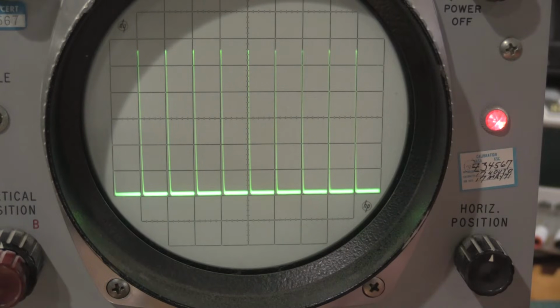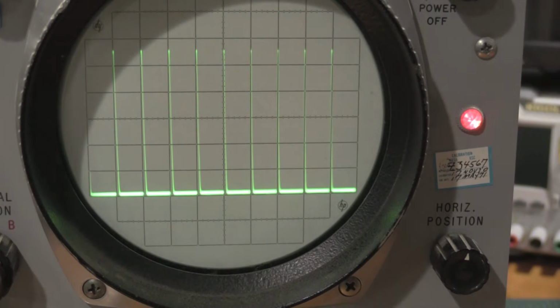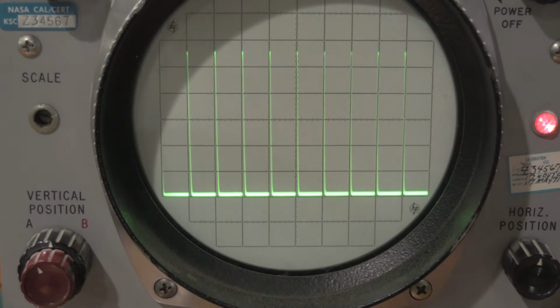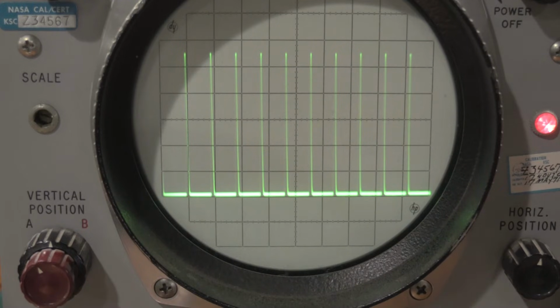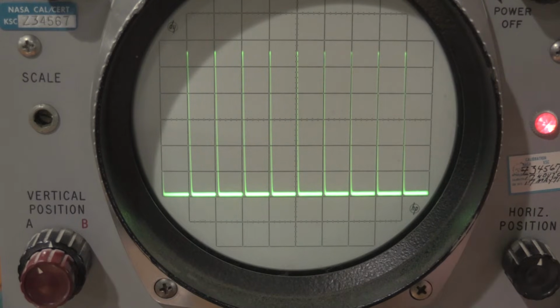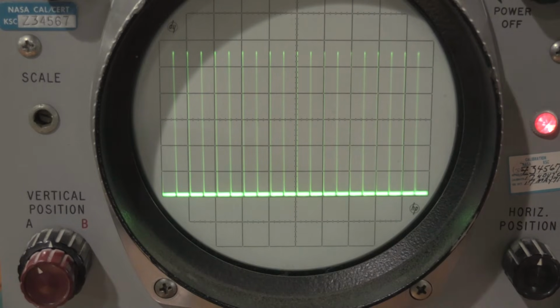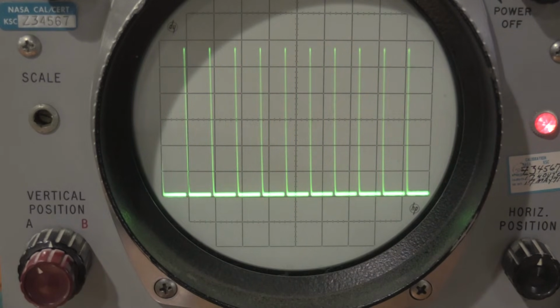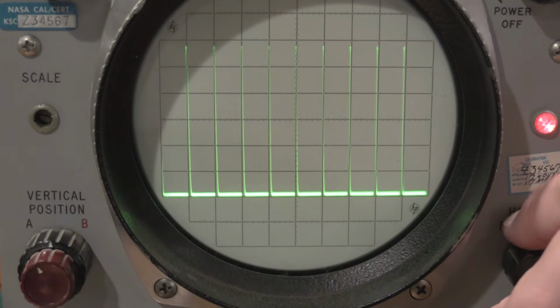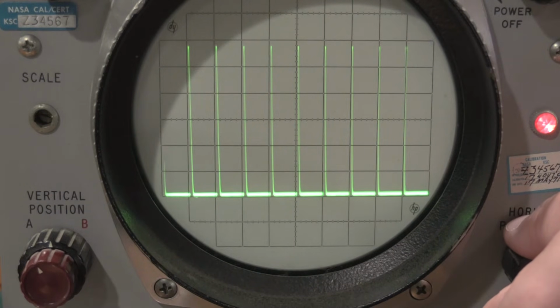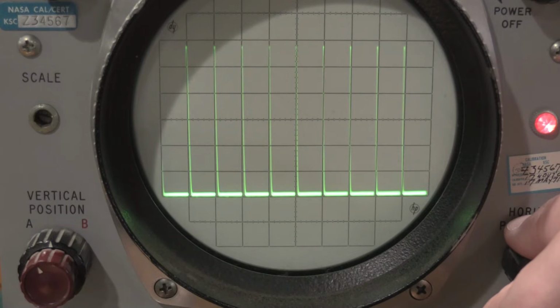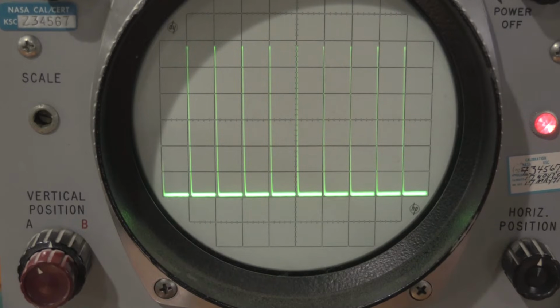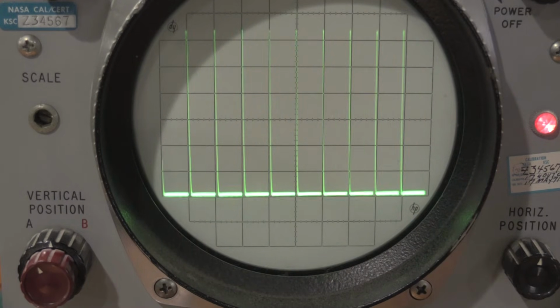As I slow the scope down, my linearity is getting better because the timing marks now line up. But this range at 50 microseconds is running 8.2% slow, because that's what the time marks want it to be. So that would need adjusting. My 50 microsecond range is out. About our 100 microsecond range, what does this look like? Yeah, that is also slow, by quite a bit. That could also be a little bit of drift over time. This thing is, wow, about 60 years old. We'll drop another range. Yeah, everything is running 8.5% slow now.